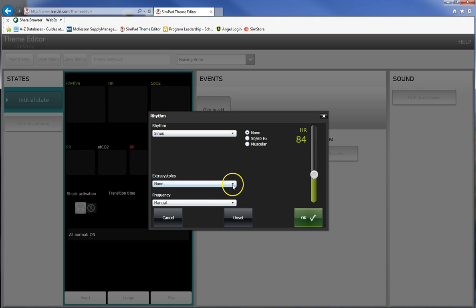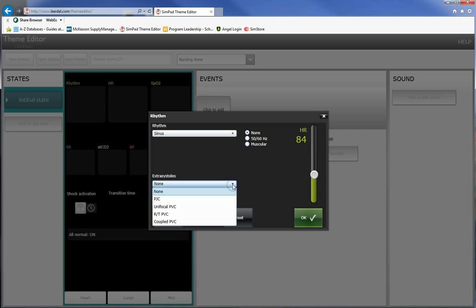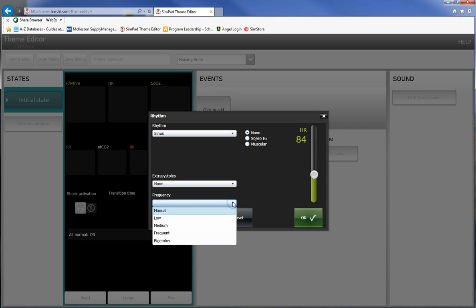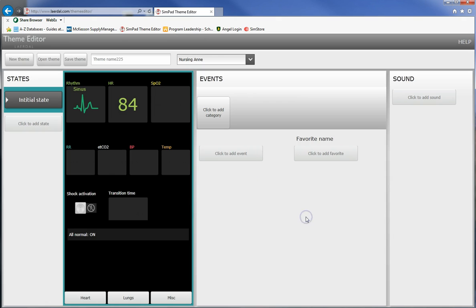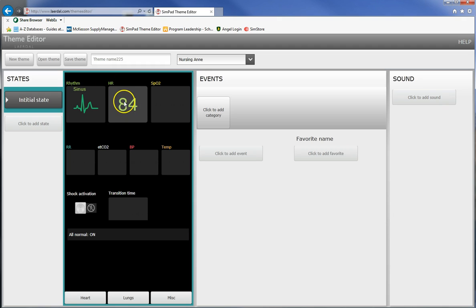We'll make this a sinus rhythm and it's going to come up with a little graphic here. Let's make the heart rate something normal so 84, that's a nice normal heart rate. Extra systoles are things like PJCs, PVCs, and you can set how often they happen. Low I believe is somewhere around twice a minute, medium is around five times, and frequent is something above 10. You can also set it to have bigeminal extra systoles, you can also set it to have 60 cycle interference and or muscular interference or motion interference.